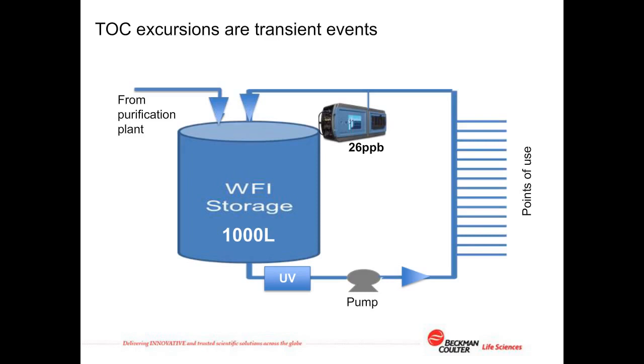In this modern water for injection system on the screen here, the TOC levels are commonly recorded around 26 parts per billion. Suddenly, a slug of TOC is fed into the water system by accident from one of the points of use, causing excursions of 750 parts per billion on all the other points of use, equivalent to 750 micrograms per liter of water. This is detected and reported by the online TOC analyzer.